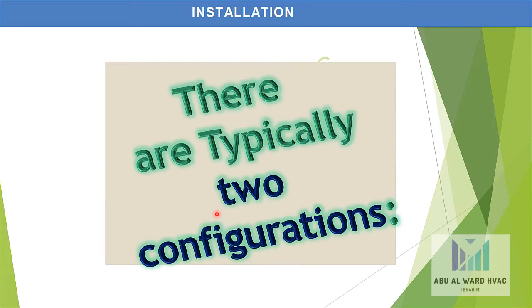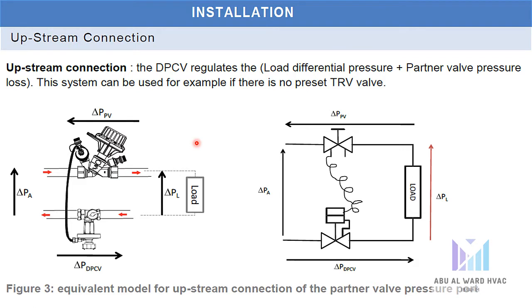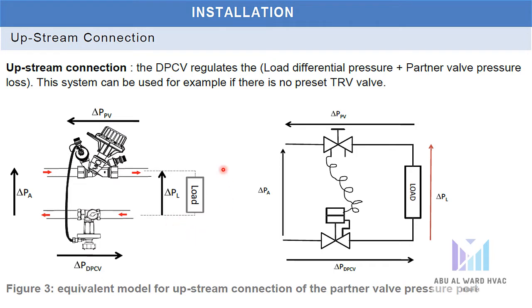For installation, there are typically two configurations. In a downstream connection, the DPCV regulates the load differential pressure only; Delta P for the DPCV equals Delta P load, which is typically Delta P A. In an upstream connection, the DPCV regulates the load differential pressure plus the partner valve pressure loss. This can be used where there is no preset TRV valve; in this case Delta P DPCV equals Delta P load plus Delta P of the partner valve.